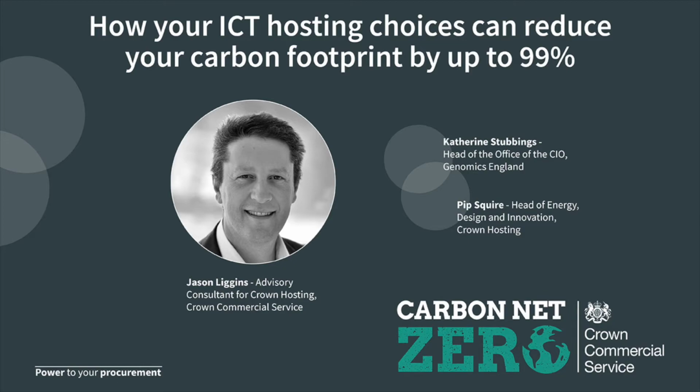And to put it into context, that's because when we're operating at above 30% of the load in the facility, 85% of all the energy that comes into the building is used by the IT equipment directly. 6% is used by cooling, 6% is used by the electrical infrastructure, and 3% is used to provide a safe and secure working environment for the staff who are required to maintain and operate the facility and our customers. So that gives you a PUE of 1.2.